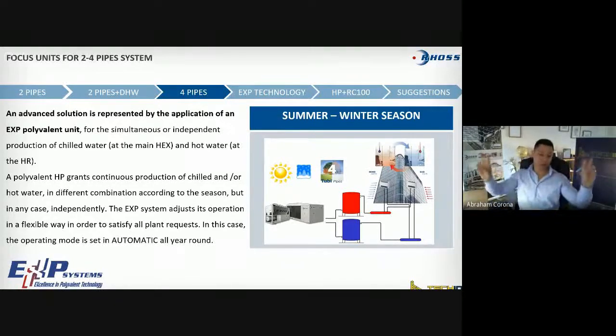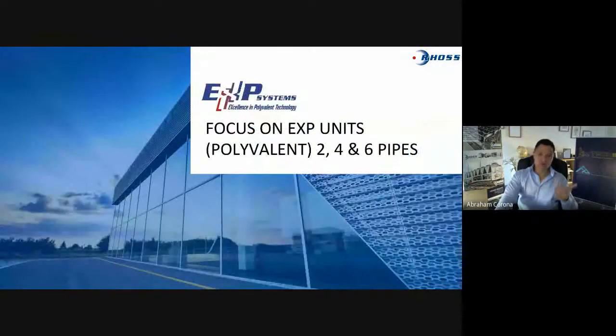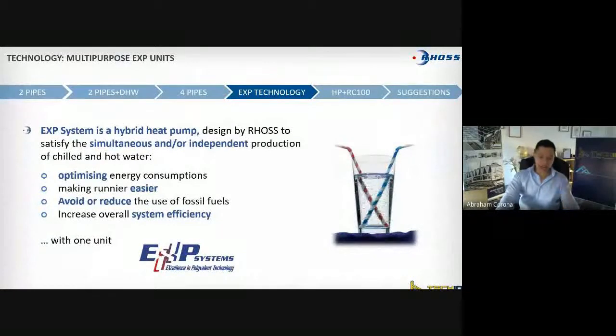Yeah, I do a parenthesis. Depending on how you want to control the system, you can control the outlet or the inlet. We can do both, and I prefer to control the outlet of the unit. So when we focus on 4-pipe units, and now we are inside RHOSS, inside what is EXP Technology is a 4-pipe unit. The EXP unit is a hybrid heat pump out of RHOSS. That is a hybrid unit able to comply with all the situations, optimizing energy, avoiding the use of fossil fuels. You may not use the boiler that often and increase system efficiency.